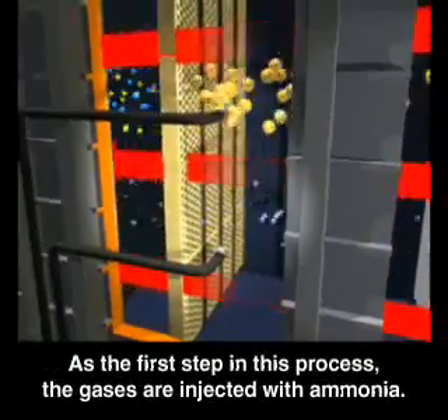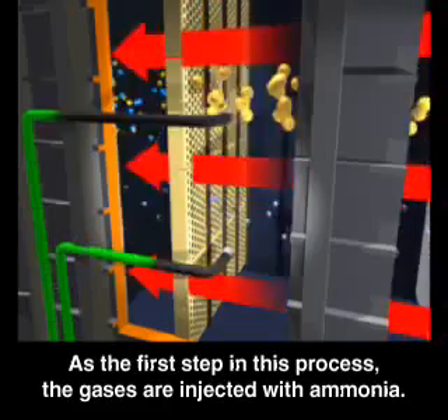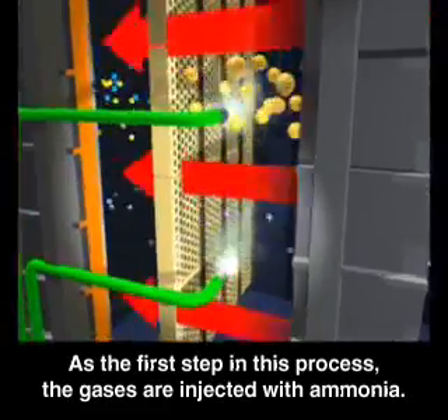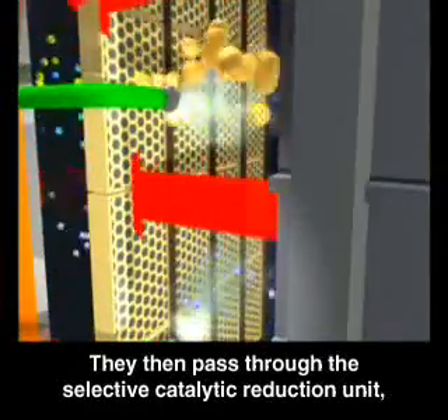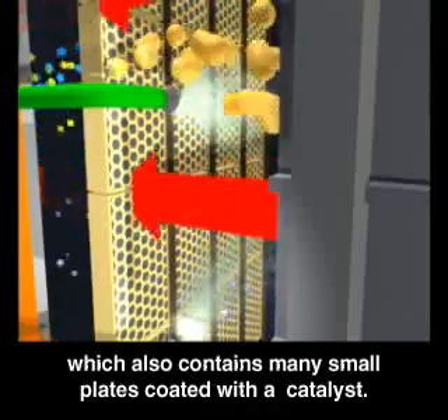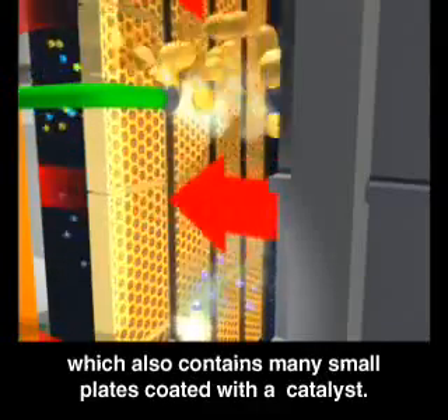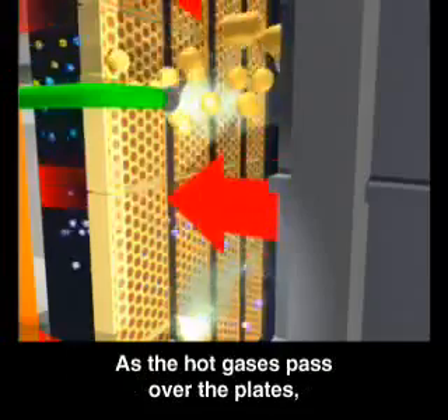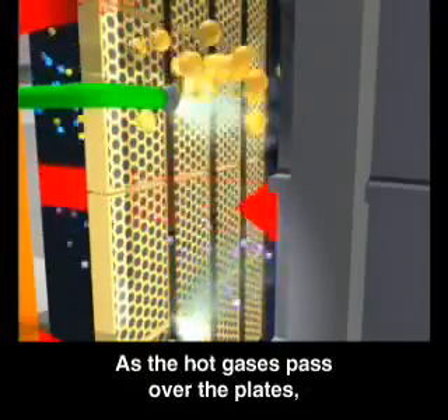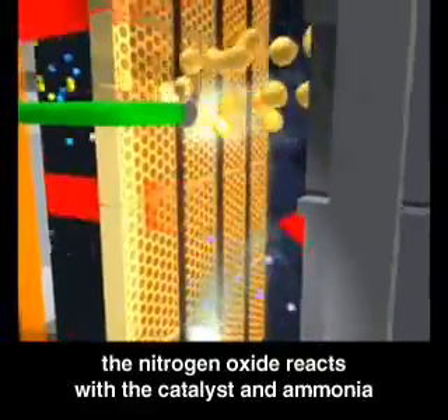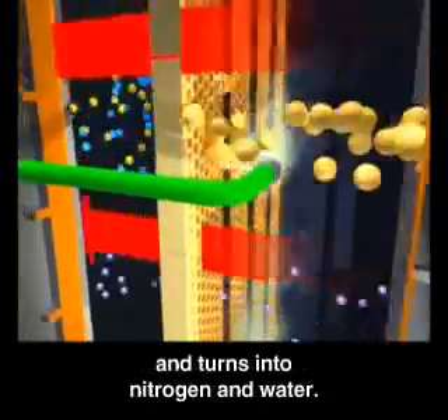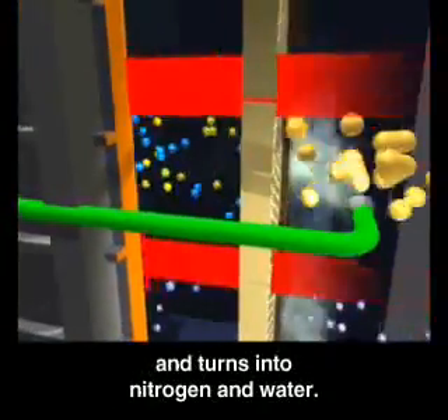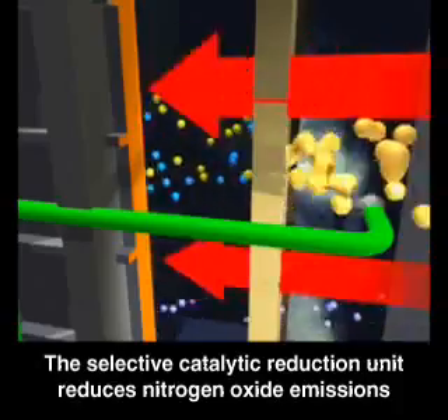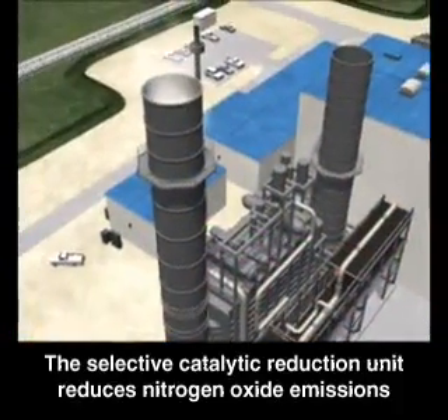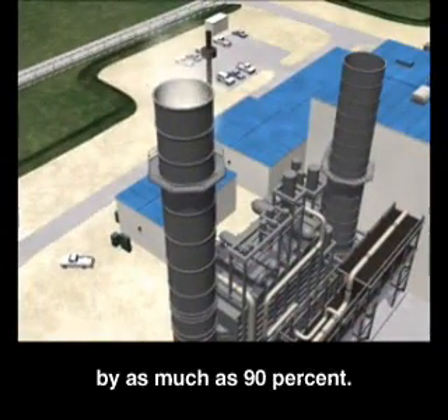As the first step in this process, the gases are injected with ammonia. They then pass through the selective catalytic reduction unit, which also contains many small plates coated with a catalyst. As the hot gases pass over the plates, the nitrogen oxide reacts with the catalyst and ammonia and turns into nitrogen and water. The selective catalytic reduction unit reduces nitrogen oxide emissions by as much as 90%.